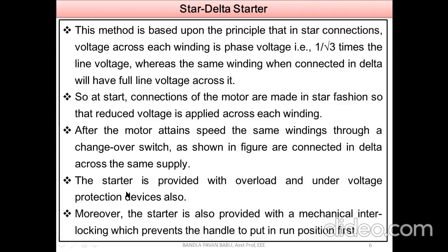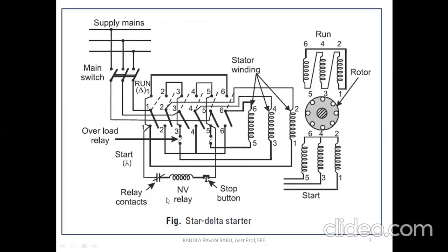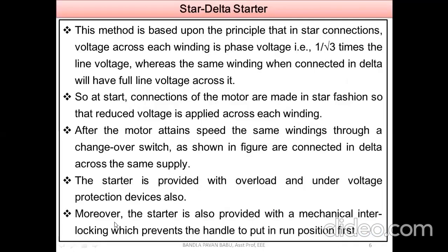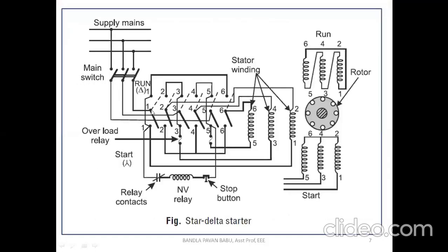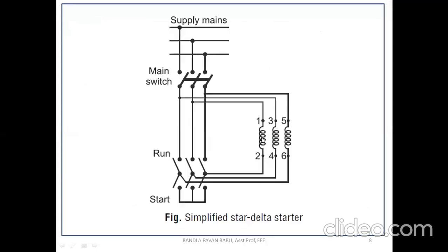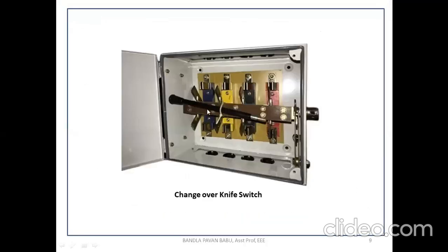Let's see the procedure. The starter is provided with overload and under voltage protection devices also. That is mentioned here. This is the no volt release coil, and this is the overload release coil or overload relay. Moreover, the starter is also provided with a mechanical interlocking, which prevents the handle from being put in the run position first. So this is the mechanical interlocking: if we provide any action there, it has to lock. I mean, the switch has to be locked.